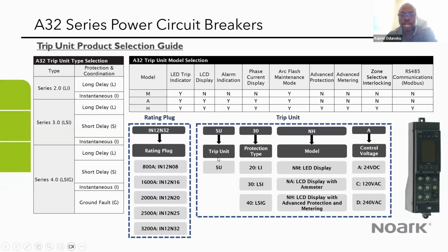But for the trip unit, here's a quick selection guide. Like I said before, the rating plug is matched with the current rating that you selected for the circuit breaker. So if you select the 1600 amps, then we will give you this rating plug. But you may decide that you want to operate your breaker at a lower capacity and request an 800 amps rating plug. For the trip unit, we have 3 types. You have the NM, which is the basic, introductory one, and then we have the LCD with ammeter function, and then the LCD with advanced protection. For all of those trip units, you have 3 types of protection: the LI, the LSI, and the LSIG. I will talk about those shortly.